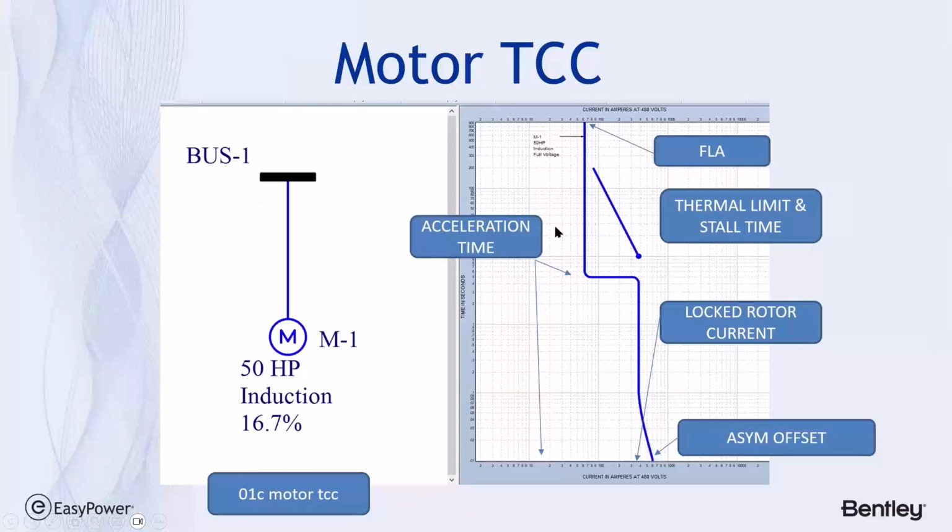So I usually refer to the fact that the left-hand side of the chart would be considered a normal start for any plot that's time and current specific. So if we take a reading of the motor current at, let's say, 200 seconds up here, and it falls anywhere less than the 100 amps, which looks like maybe 80 amps, I take that back, maybe it's 8 amps, any current in that range at that time would be considered a normal start.